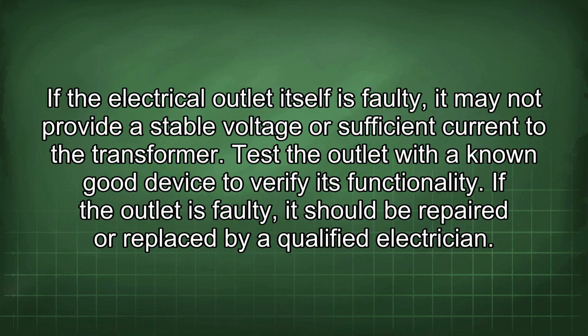If the electrical outlet itself is faulty, it may not provide a stable voltage or sufficient current to the transformer. Test the outlet with a known good device to verify its functionality. If the outlet is faulty, it should be repaired or replaced by a qualified electrician.